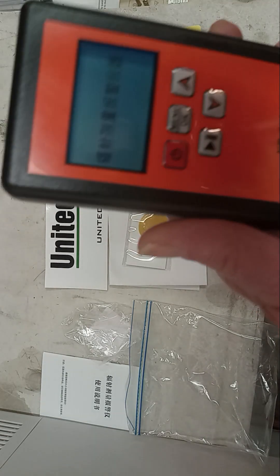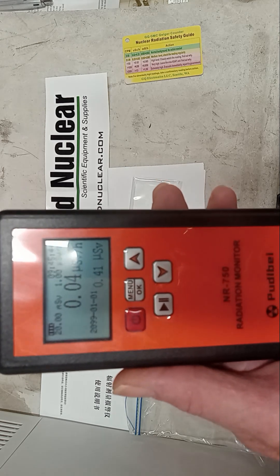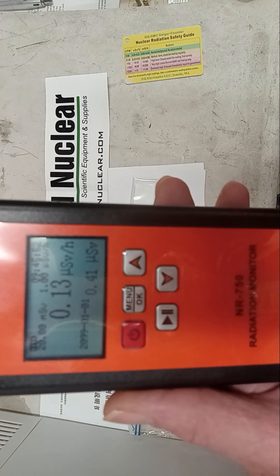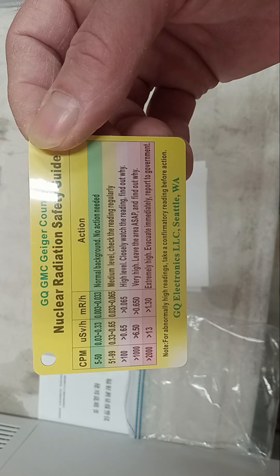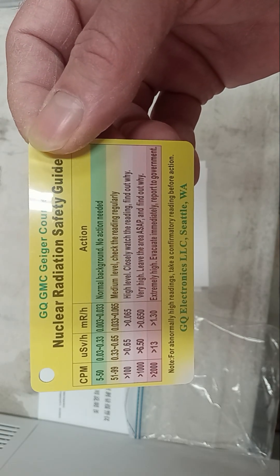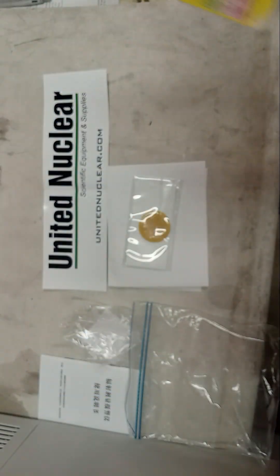You may let it sit for a year, throw some batteries in it, and now you can't remember what you're supposed to know. The device does have an alarm, so let's move it away from our source. Our background radiation will slowly count up — it'll probably get to around 0.10 and float around a little bit. There's constant radiation around you. When we look at our RAD card, in micro sieverts — USV/H — the green zone goes all the way up to 0.33, and we are green here, far enough away from our source.